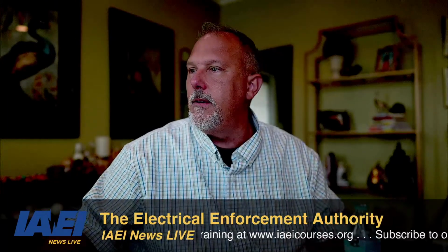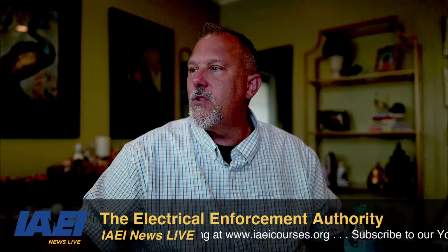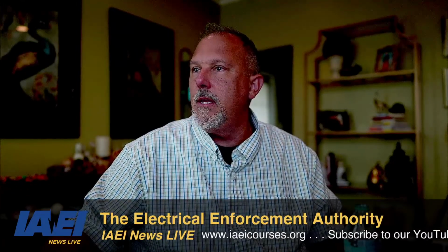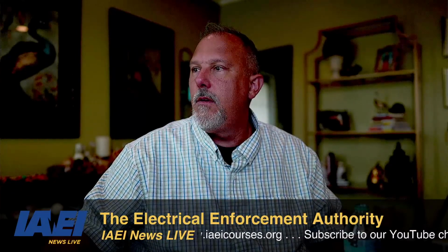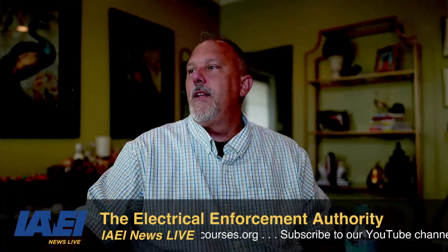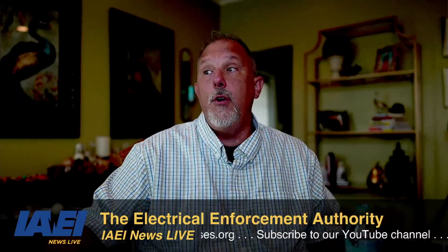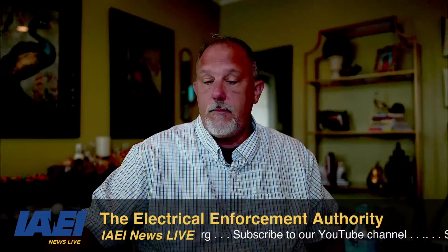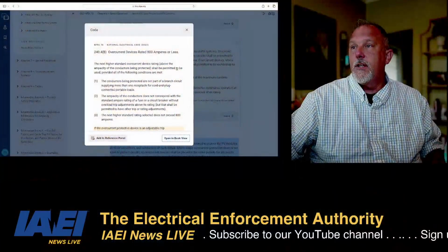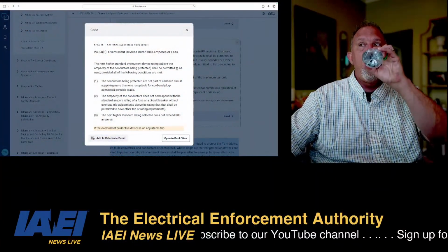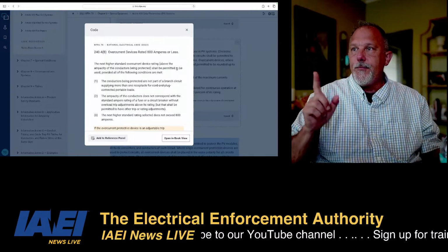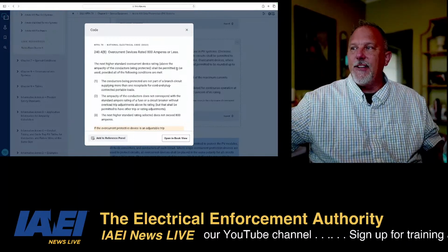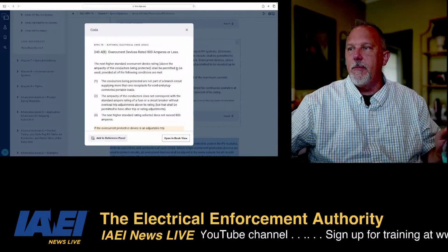Don Ganir. In accordance with 240.4b, the following are permitted to be rounded. Oh no, hold on, Dawn. So here's the issue. The next higher standard overcurrent device rating shall be permitted to be used.